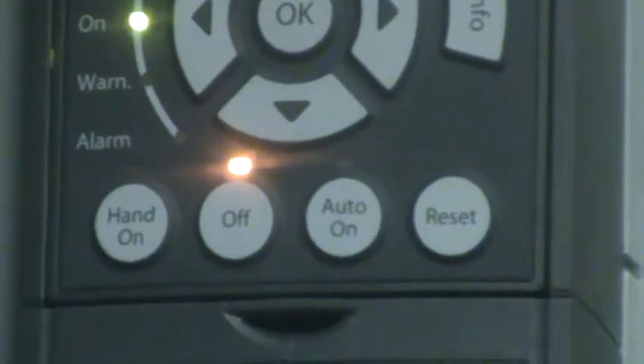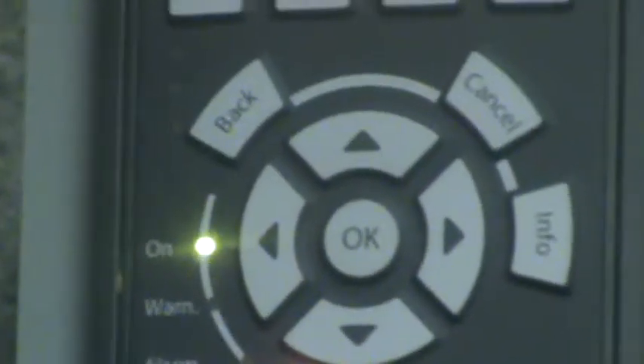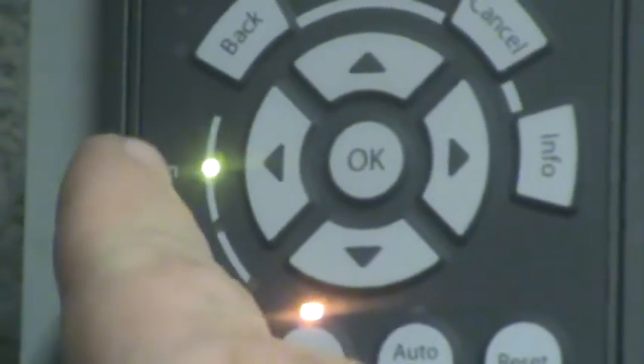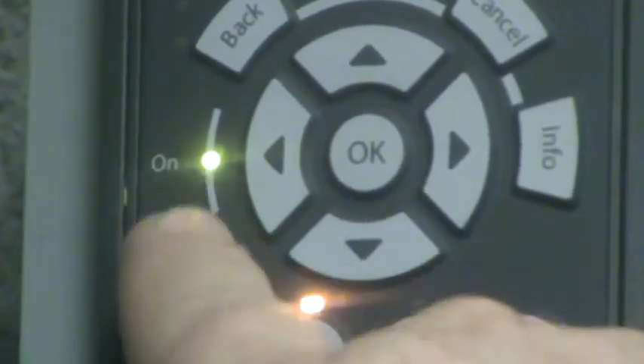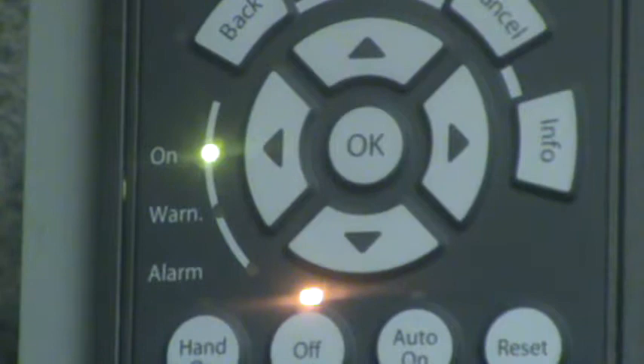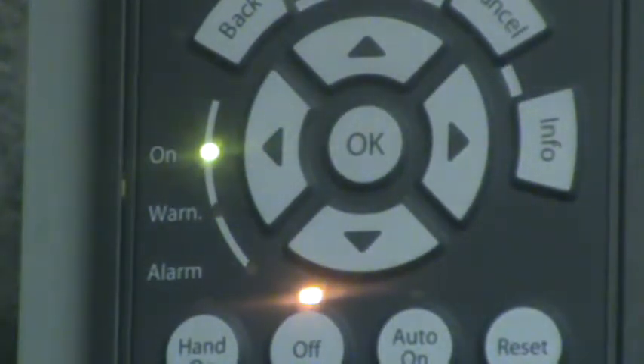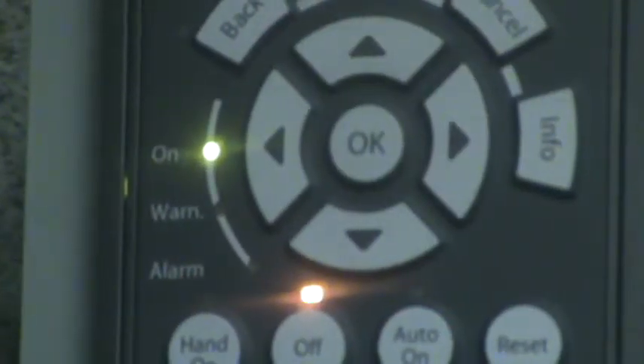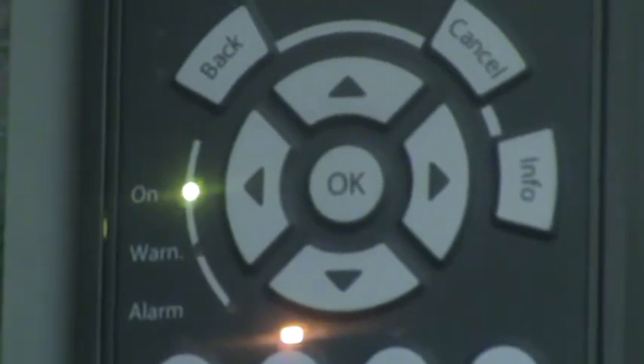Explain the warning lights. Now, on the side here, the little green light will always be lit up. Underneath here is warning and alarm. If the drive senses something it doesn't like, in most cases it'll first give you a warning. If your current's off or your voltage is funny, it'll go into a warning state. You'll get a description across the bottom here that says warning, and then whatever the problem is.